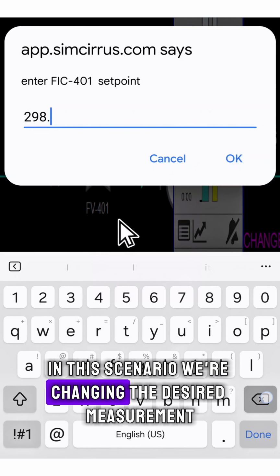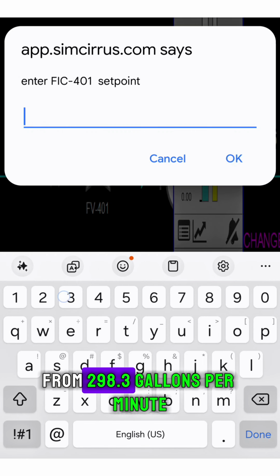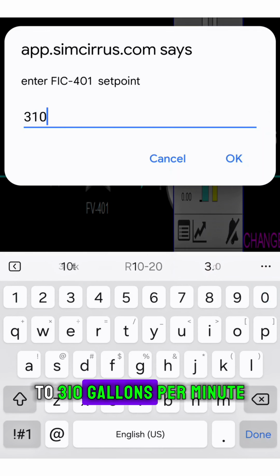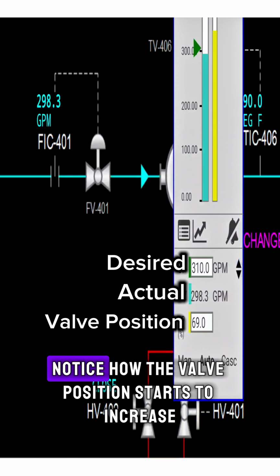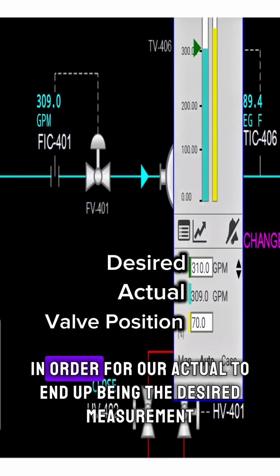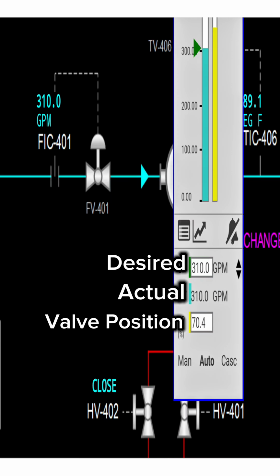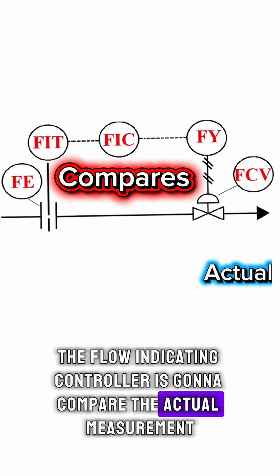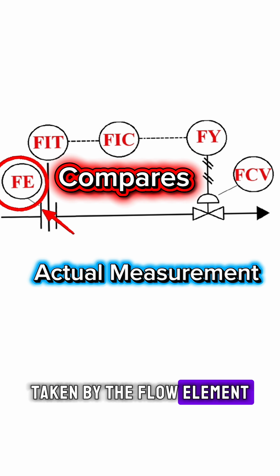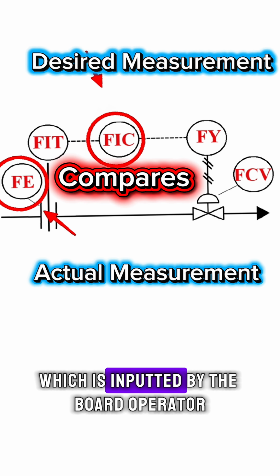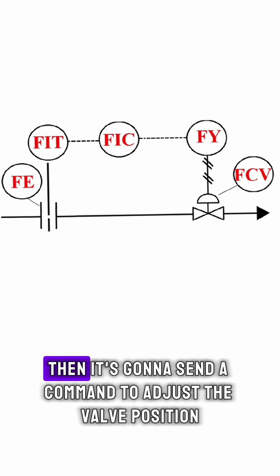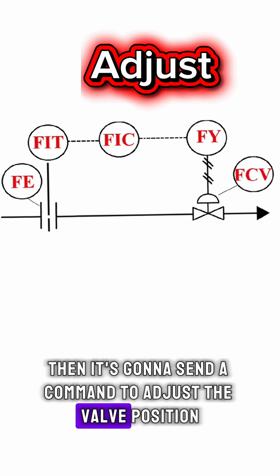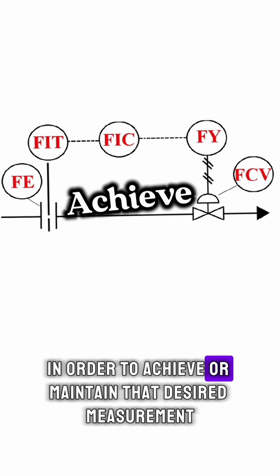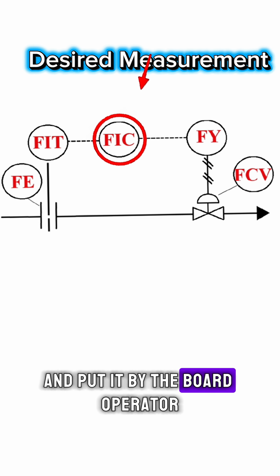In this scenario, we're changing the desired measurement from 298.3 gallons per minute to 310 gallons per minute. Notice how the valve position starts to increase. In other words, the valve is actually opening in order for our actual to end up being the desired measurement. The flow indicating controller is going to compare the actual measurement taken by the flow element with the desired measurement, which is inputted by the board operator. Then it's going to send a command to adjust the valve position in order to achieve or maintain that desired measurement inputted by the board operator.